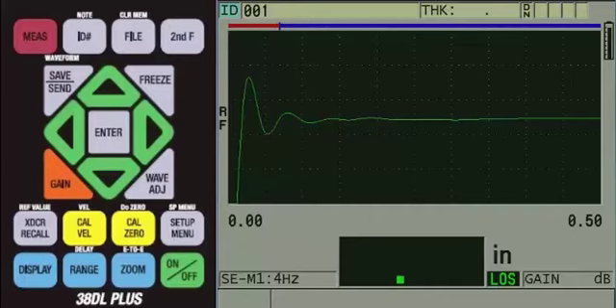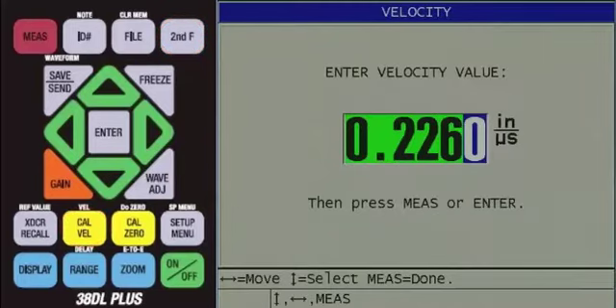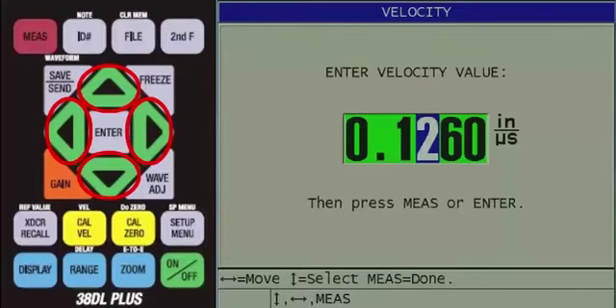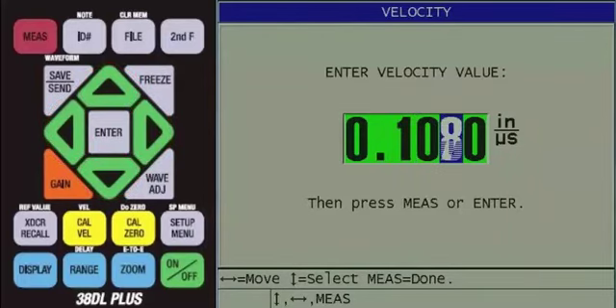The default setup we recalled has a default sound velocity for stainless steel, so we need to change it to something closer to fiberglass. To do this, press and release the second F key first, and then press the Cal-Vel key. The stainless steel velocity is 0.2260 inches per microsecond, or if you are using metric units, it will be 5.740 millimeters per microsecond. Use the arrow keys to change this value to the approximate sound velocity for fiberglass, which is 0.108 inches per microsecond, or if you are using metric units, it will be 2.743 millimeters per microsecond. Then press the red measure key.